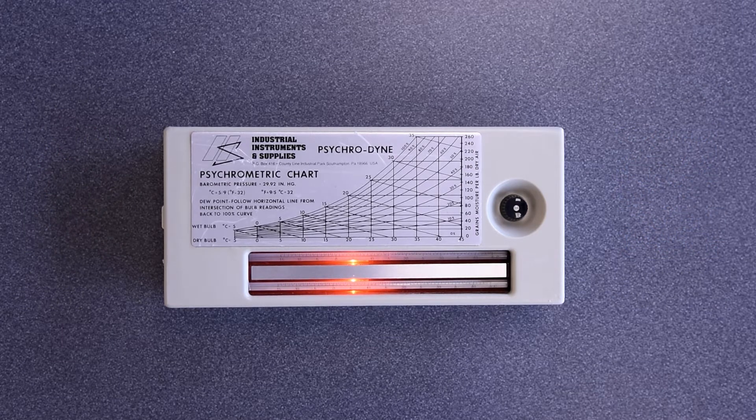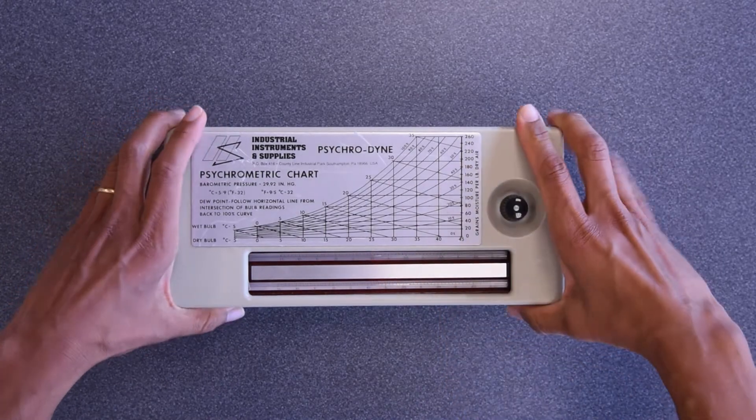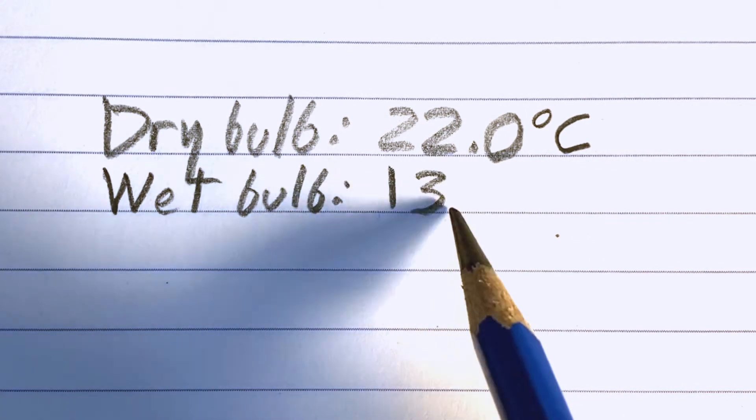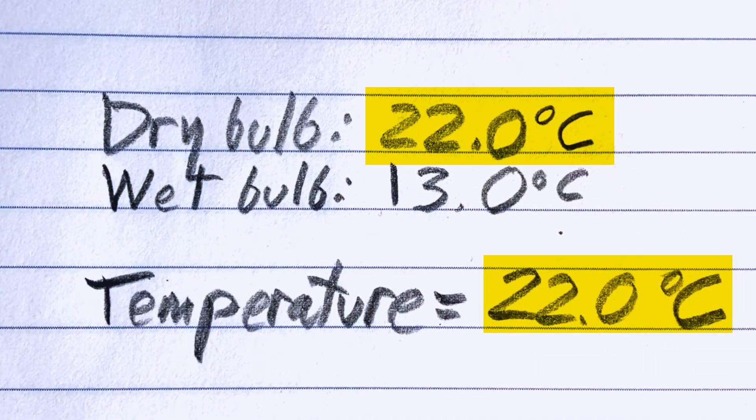Once the wet bulb temperature has settled, turn the instrument off by rotating the knob clockwise. Immediately record the values of both the dry and wet bulb temperatures. The dry bulb temperature is the temperature of the space.